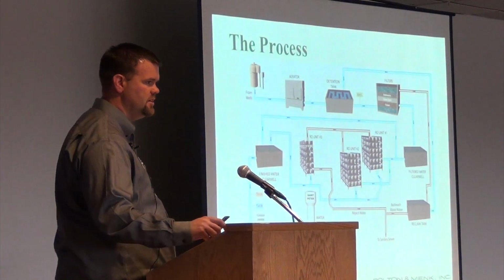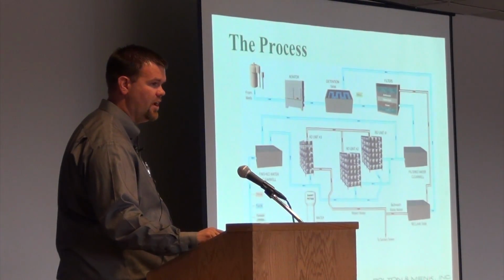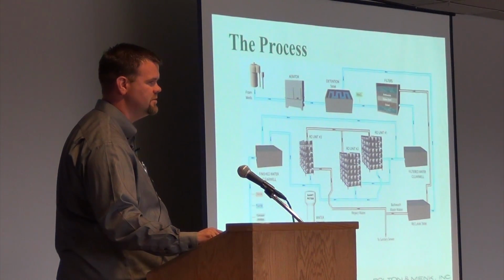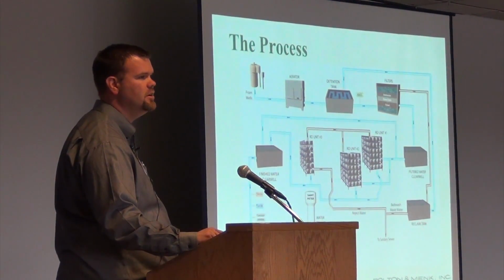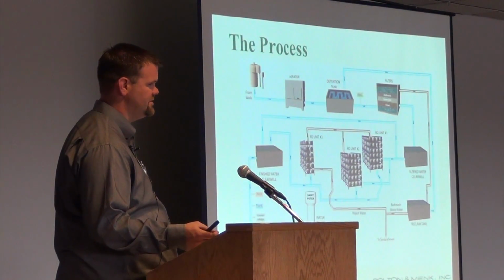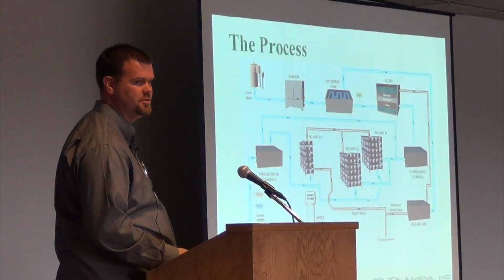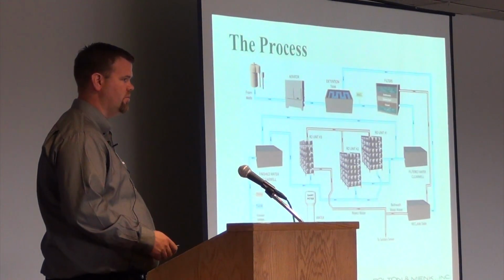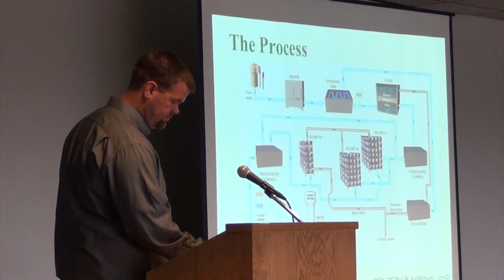In St. Peter's case, their hardness is about 5 milligrams per liter. It starts at about 24 milligrams per liter at this facility. So we're cutting it down by 80%, essentially. So if you go back to that idea of how many bags of salt I showed and how much was getting trucked into St. Peter, through public education and teaching people and helping them set the softeners lower, they're able to reduce that salt going through the wastewater plant by 80% from these sources in water treatment.